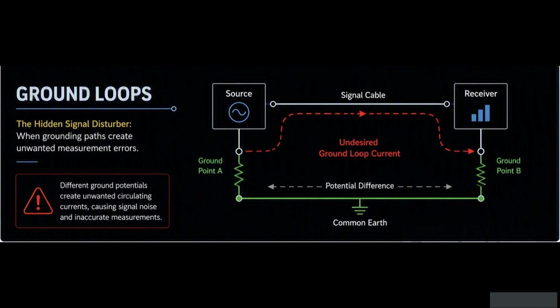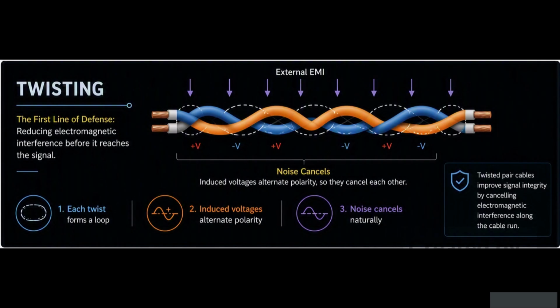The key point is that not all grounding connections are equal. Differences in ground potential can create unintended current paths that interfere with system performance. Twisted pair wiring is one of the simplest and most effective methods for reducing electromagnetic interference, or EMI, in signal cables. Each twist in the cable forms a small loop.